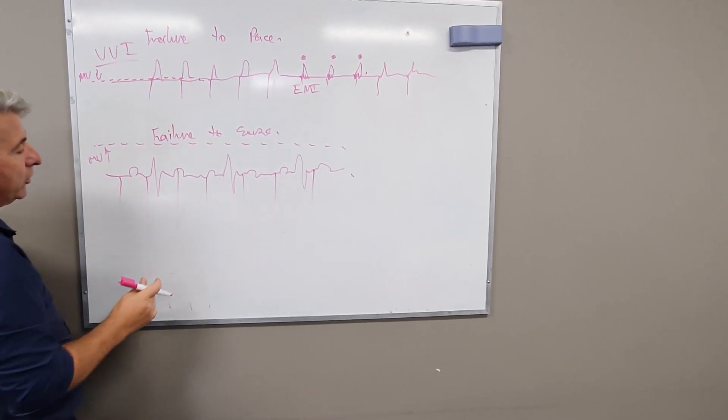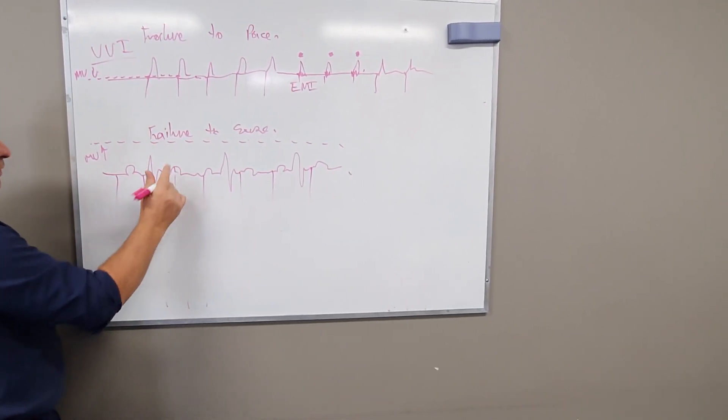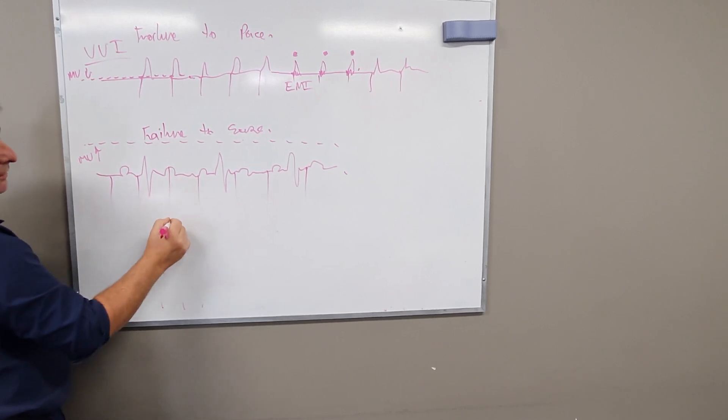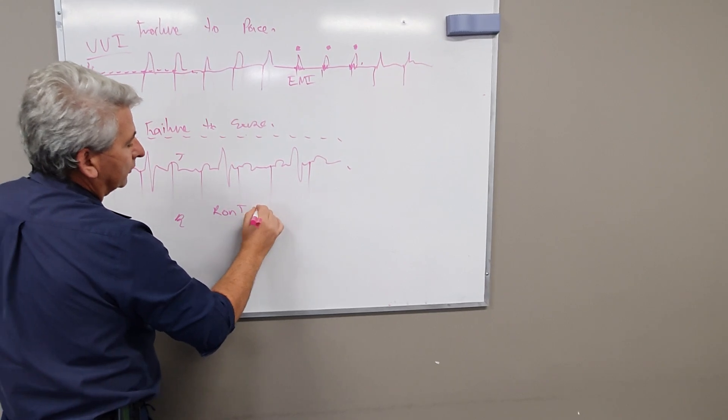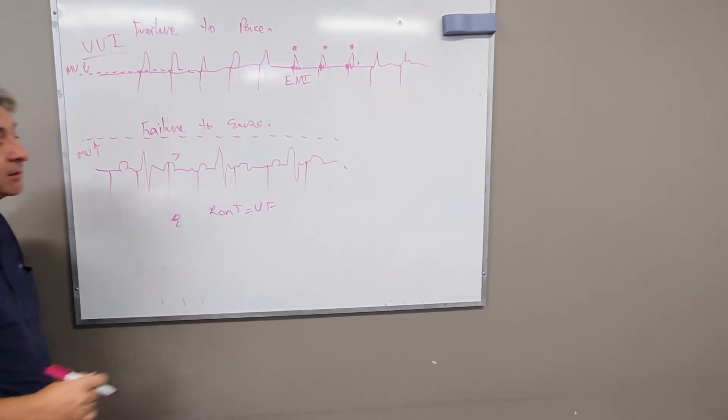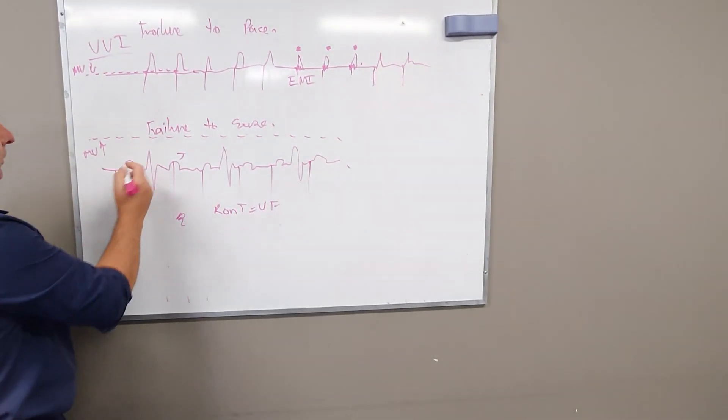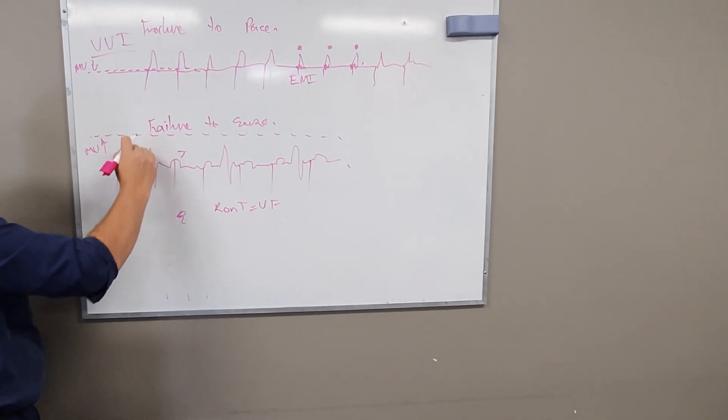Now this isn't capturing because it's not on enough, but here is what we call the R on T. So this is the R, that's your T wave. R on T will usually equal something entertaining. So what you need to do is bring the fence down or bring the millivolts down.